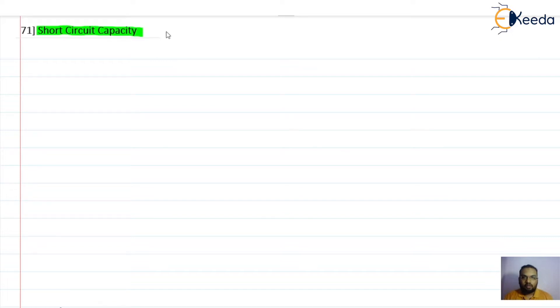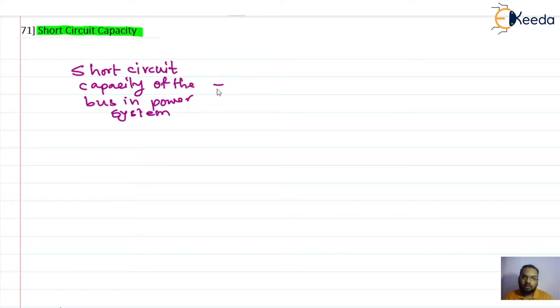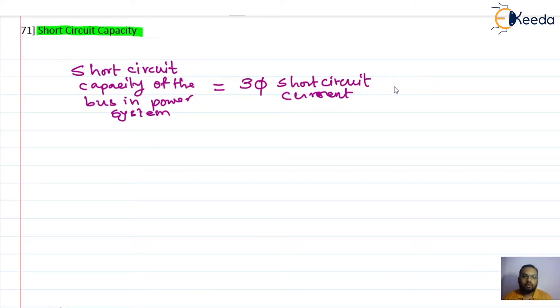Basically, short circuit capacity is used while deciding the sizing of the circuit breaker, but it can also be used to analyze voltage stability. The basic definition: the short circuit capacity of the bus in a power system is calculated as the three-phase short circuit current multiplied by the rated voltage of the bus.